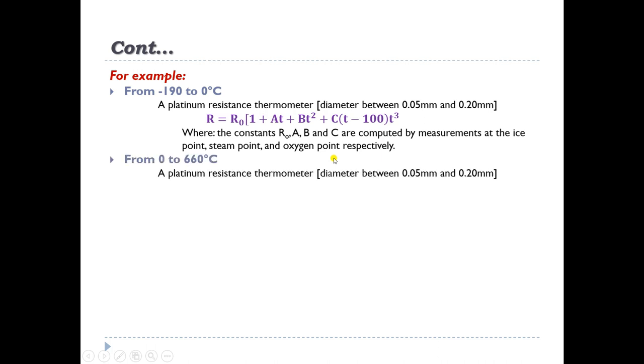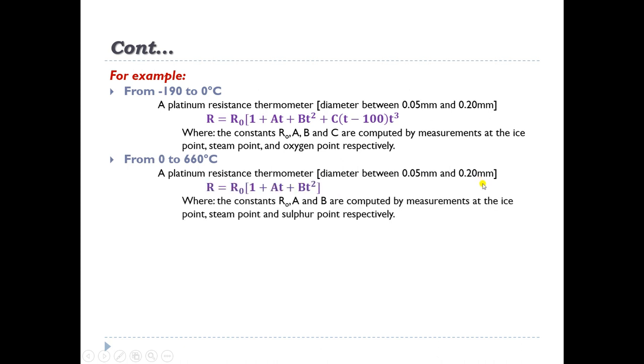From 0°C to 660°C, a platinum resistance thermometer with wire diameter between 0.05 mm and 0.20 mm is used. The polynomial equation used is R = R₀(1 + AT + BT²), where the constants R₀, A, and B are computed from measurements at the ice point, steam point, and sulfur point respectively.